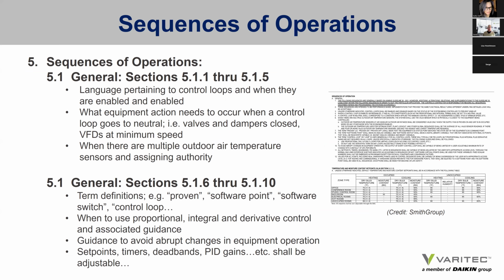The sequences in the sections 5.1.1 through 5.1.5 offer language pertaining to control loops when they are enabled and disabled. I should have said, there's a typo.